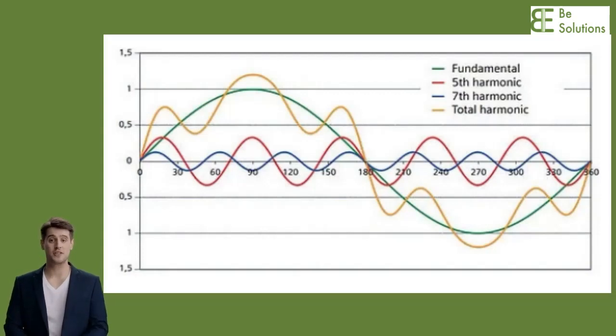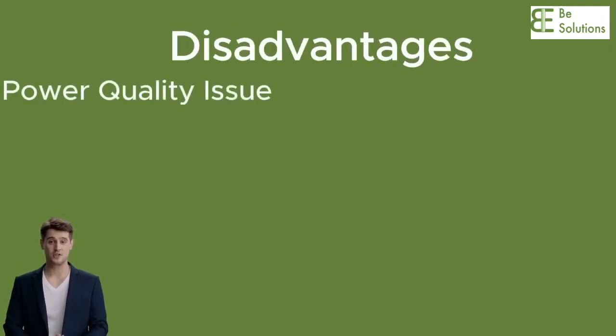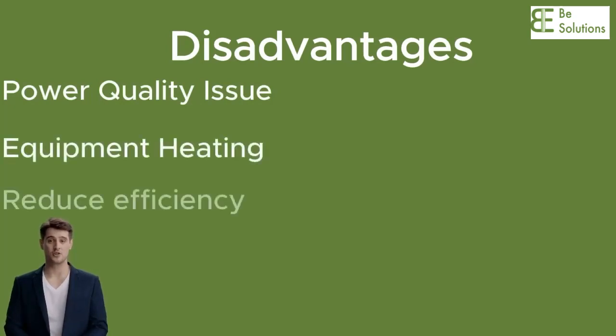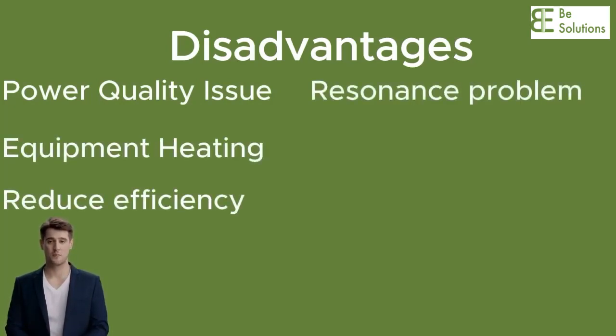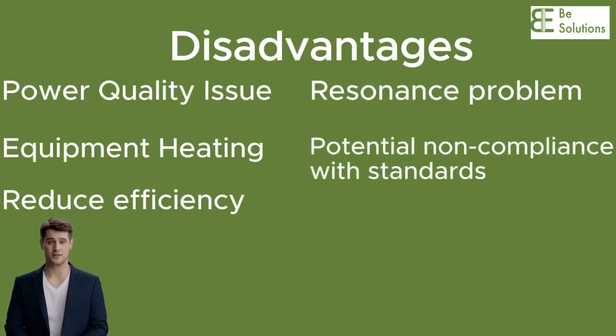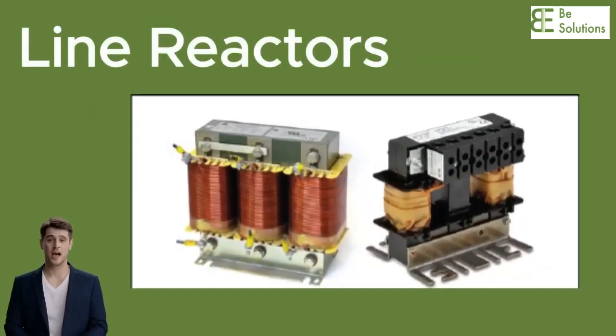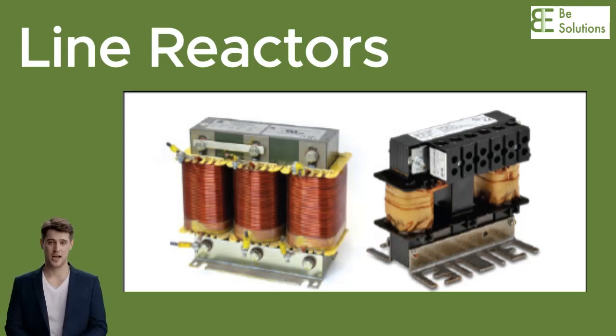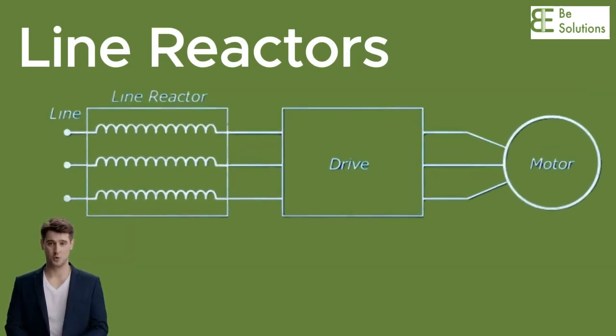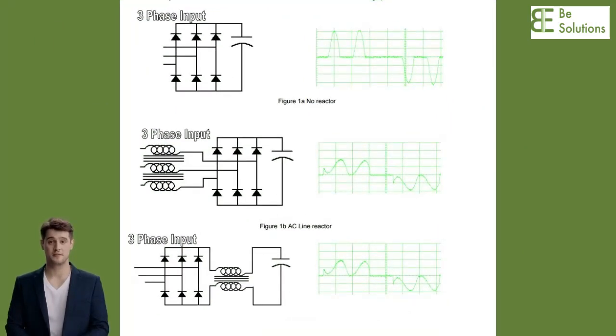Harmonics in VFDs pose disadvantages, including power quality issues, equipment heating, interference with electronics, reduced efficiency, resonance problems, and potential non-compliance with standards. To control harmonics, filters are often used. Line reactors. By inserting a line reactor in series with the load or power source, it acts as a low-pass filter. It allows the fundamental frequency and lower-order harmonics to pass through while attenuating or blocking higher-order harmonics. Line reactors are relatively simple and cost-effective solutions for reducing harmonics.